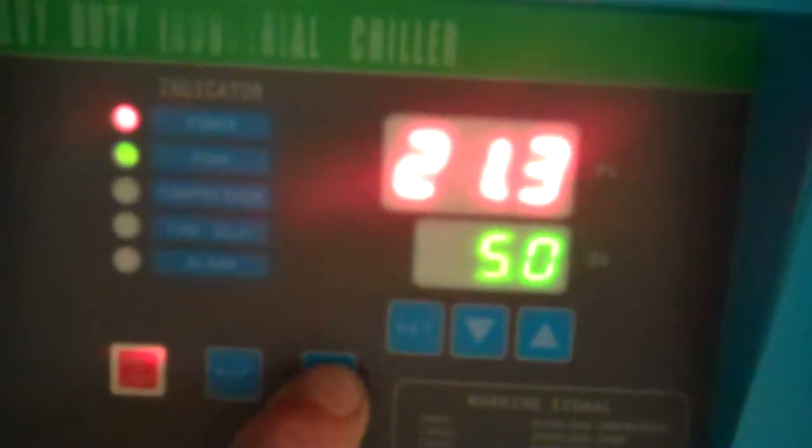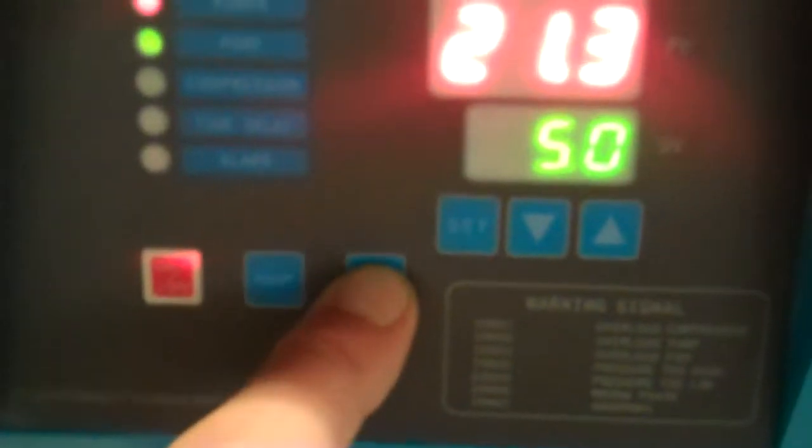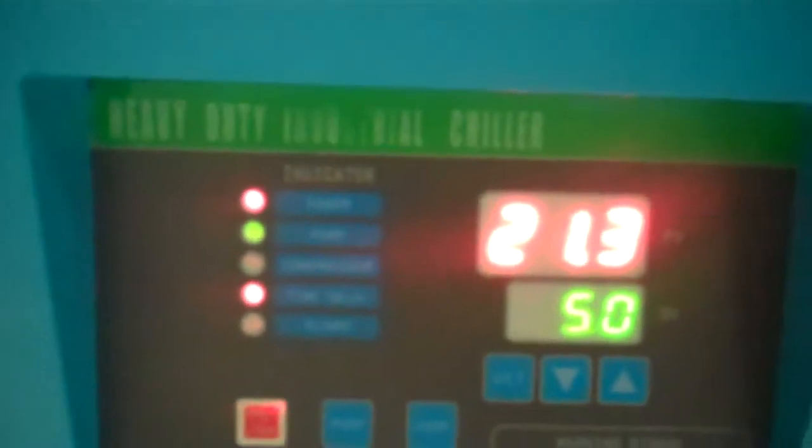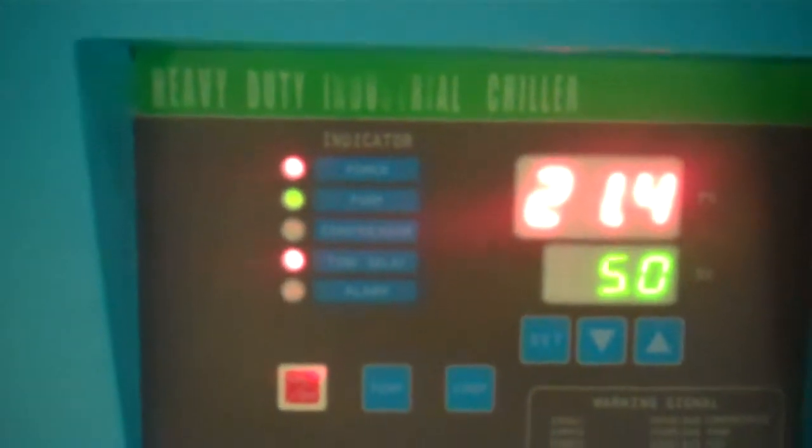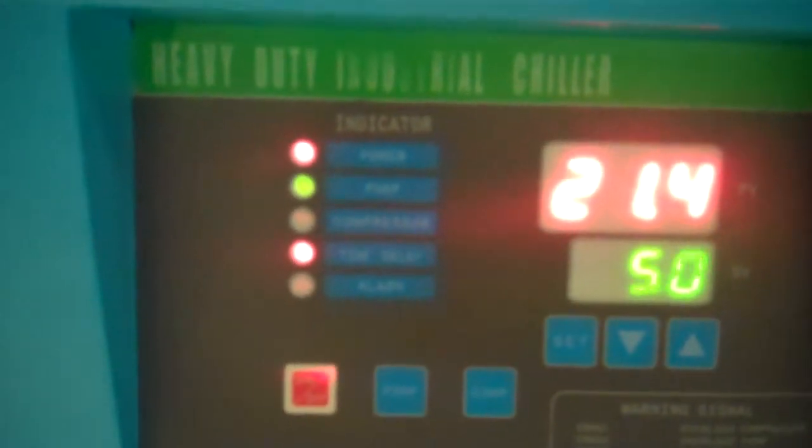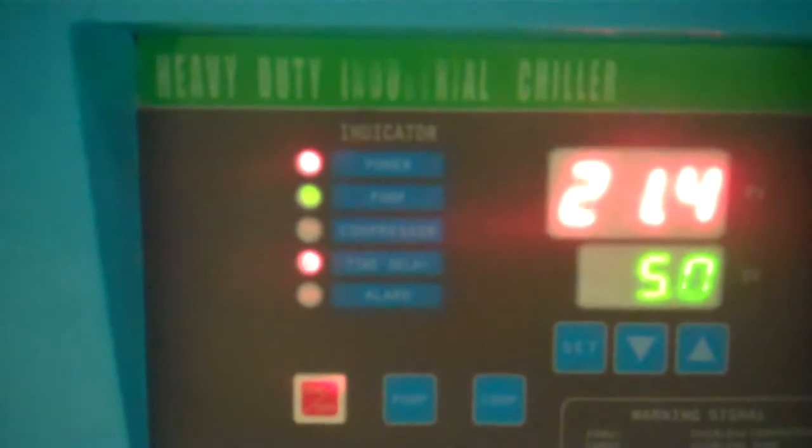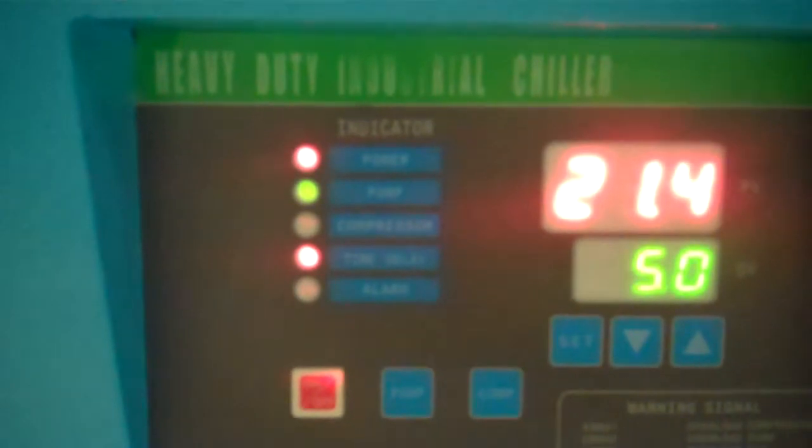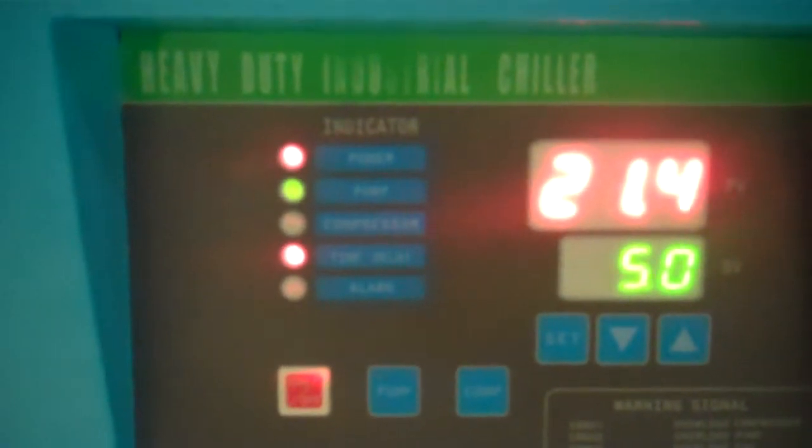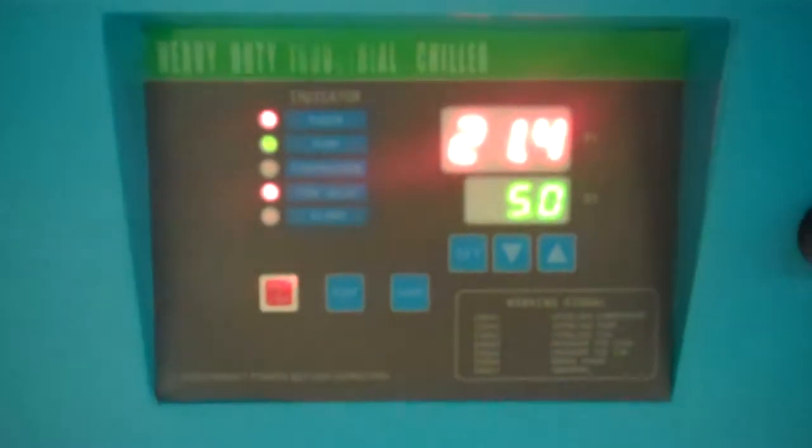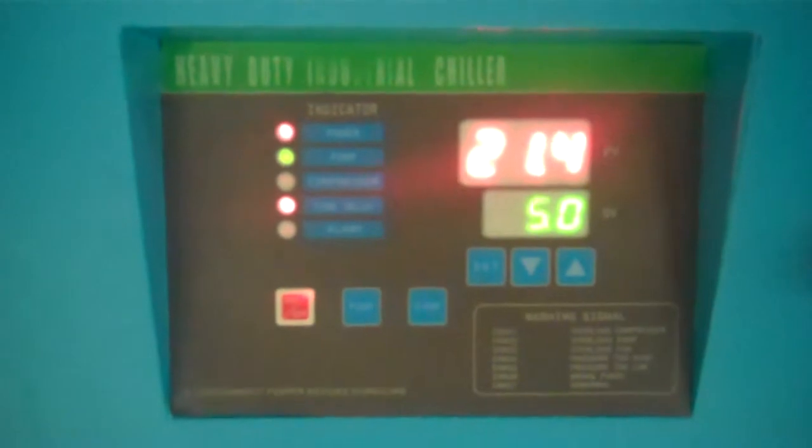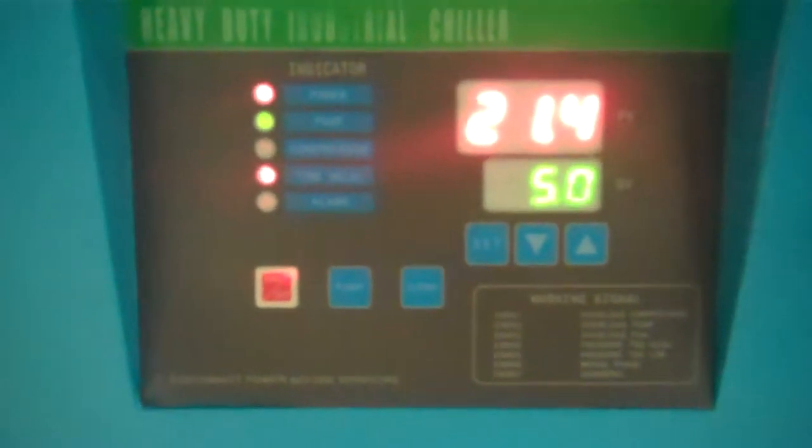Then you turn compressor on. Now there's a time delay, about 2 minutes built into these chillers. So it's going to take about 2 minutes or so, 2 minutes, 15 seconds for it to turn on. That's just a safety mechanism built right into the system.